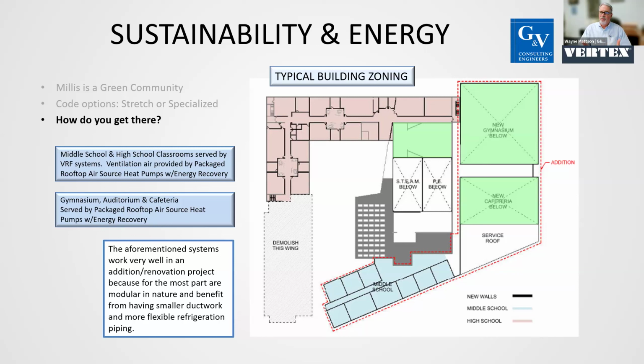It operates on what's called the demand controlled ventilation sequence, which is CO2 based. So as kids are in the spaces breathing, they produce CO2. Sensors on the wall indicate whether you need to bring more fresh air in the building, or you can get away with less fresh air as an energy savings method. And then, of course, the salmon color is in the existing building, the classroom section.